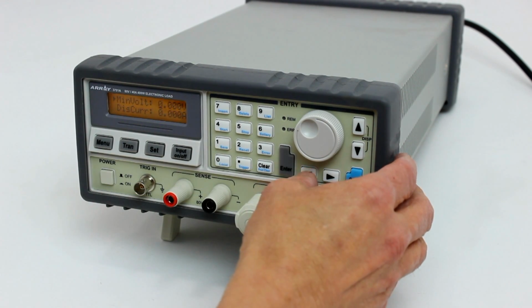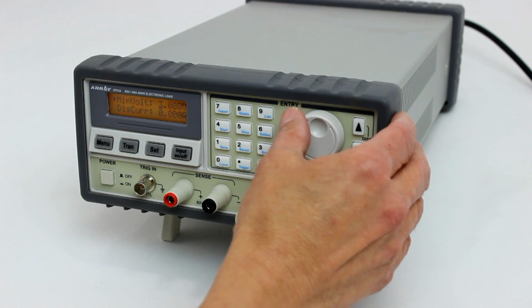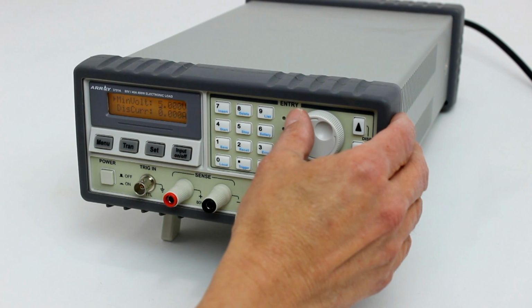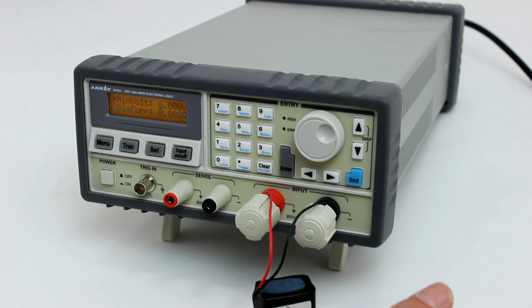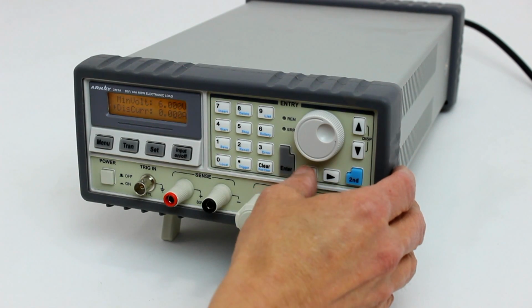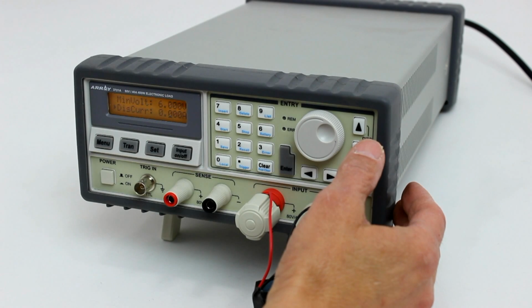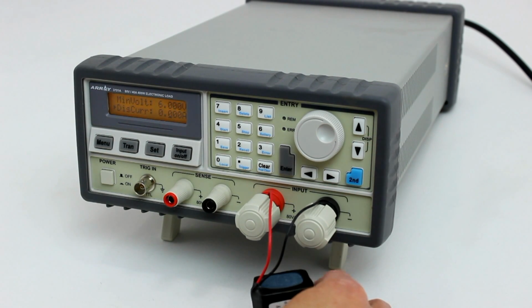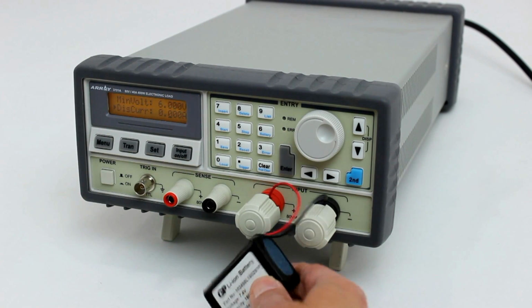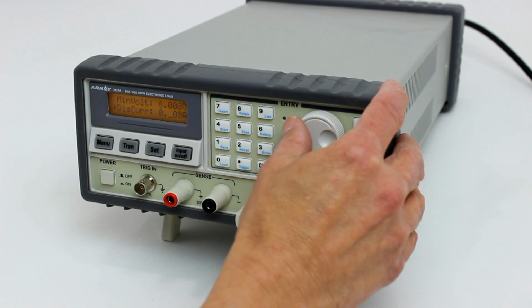Step 3. Press the set button and enter the desired discharge parameters, using the up and down buttons to select the parameter, and the left and right buttons together with the rotary knob or numeric keypad to enter desired values for termination voltage and discharge current. Press the enter button when each of the desired parameter values is displayed to lock it in memory. Step 4. Press the clear button to exit the parameter entry screen.